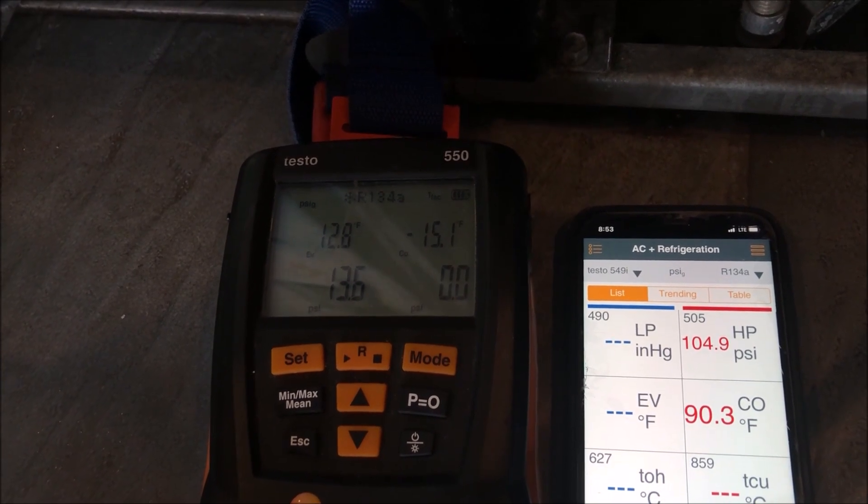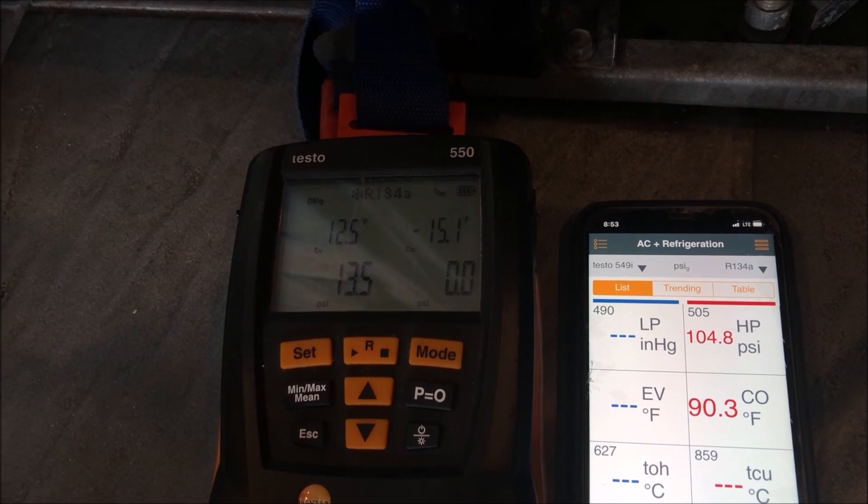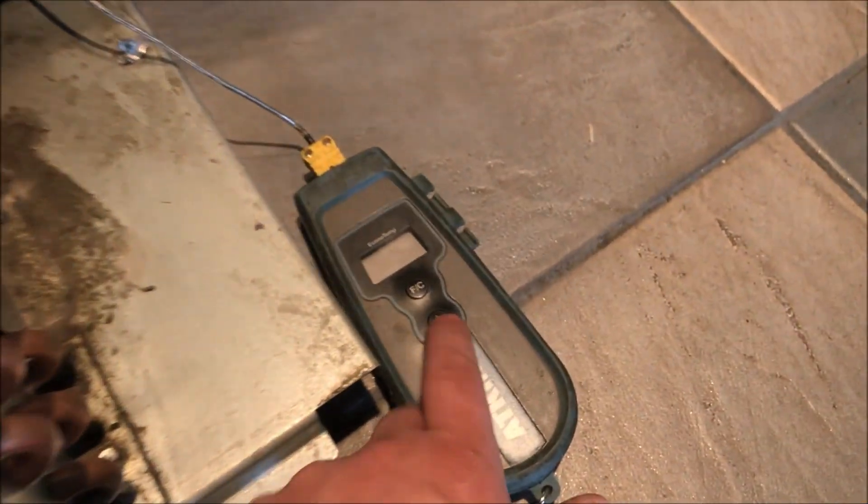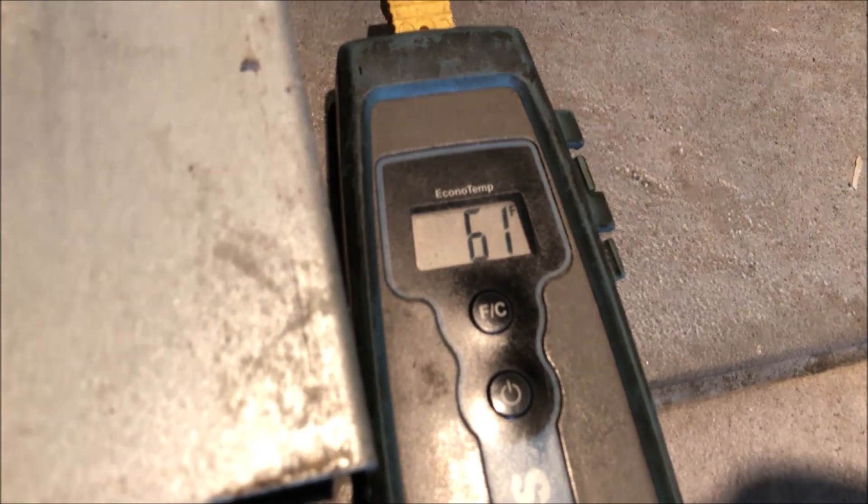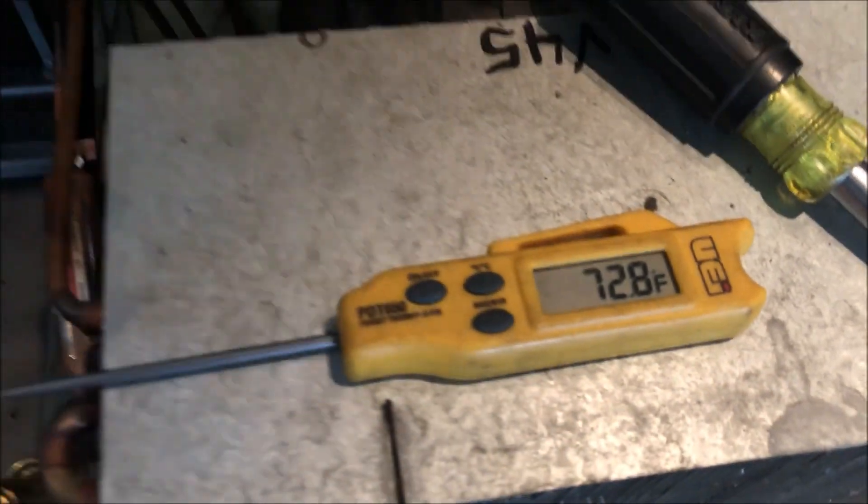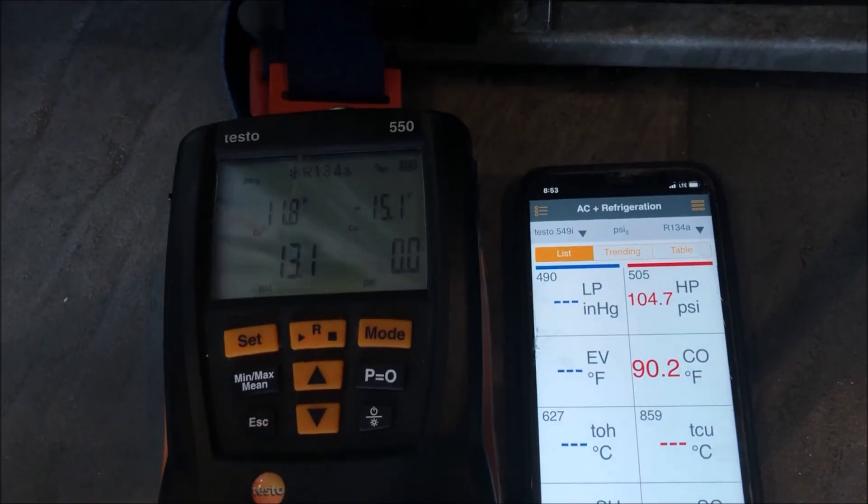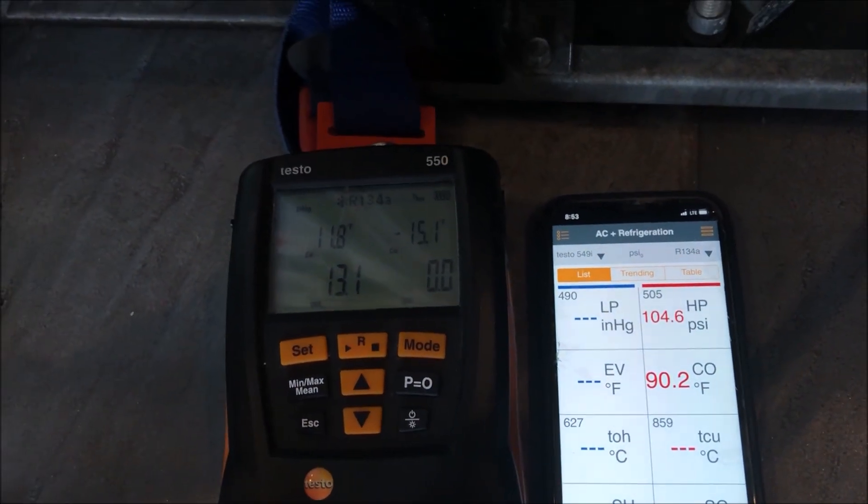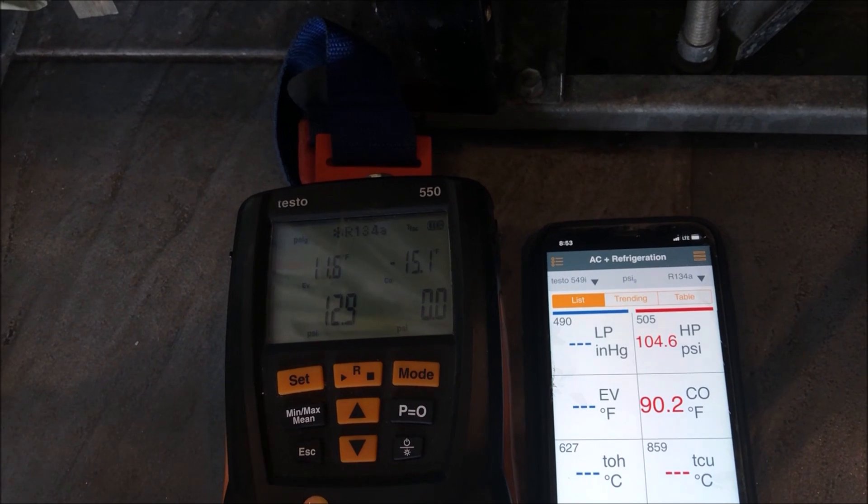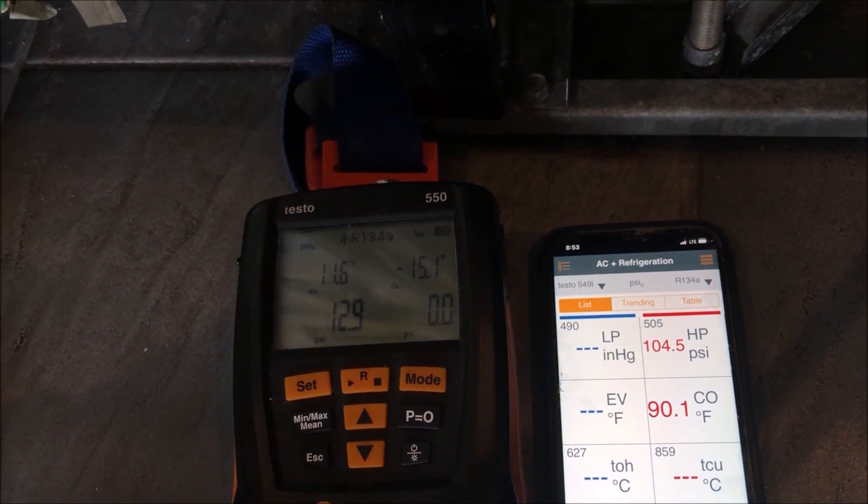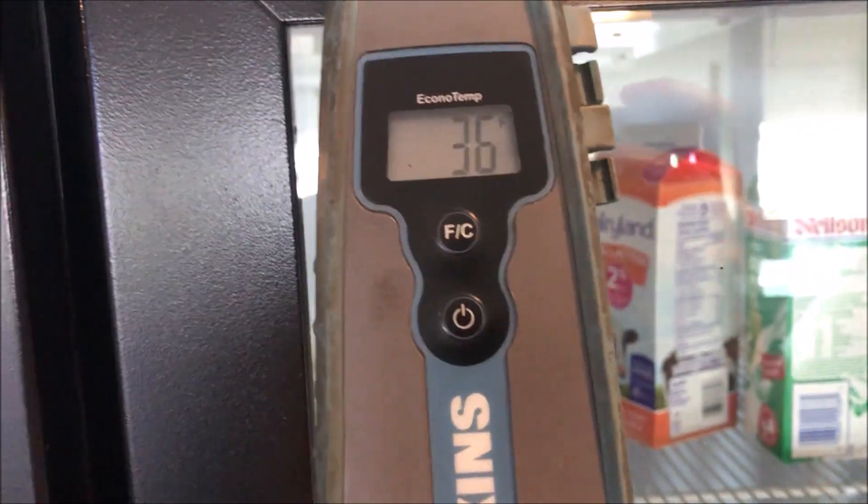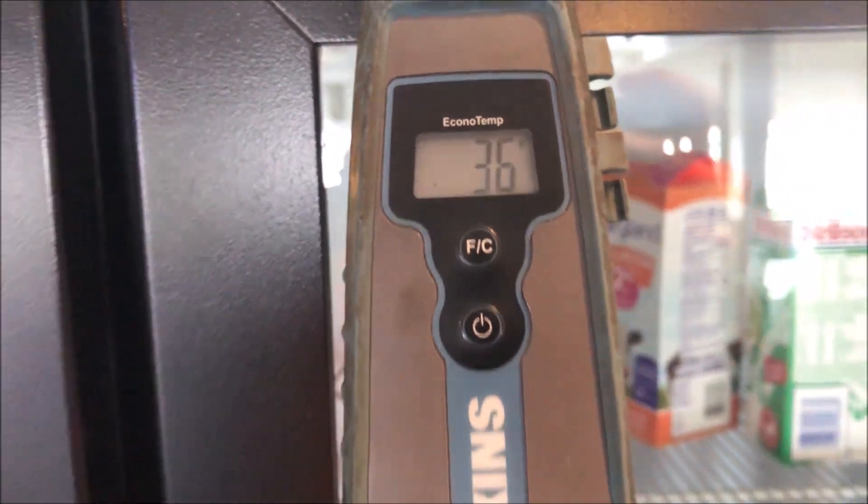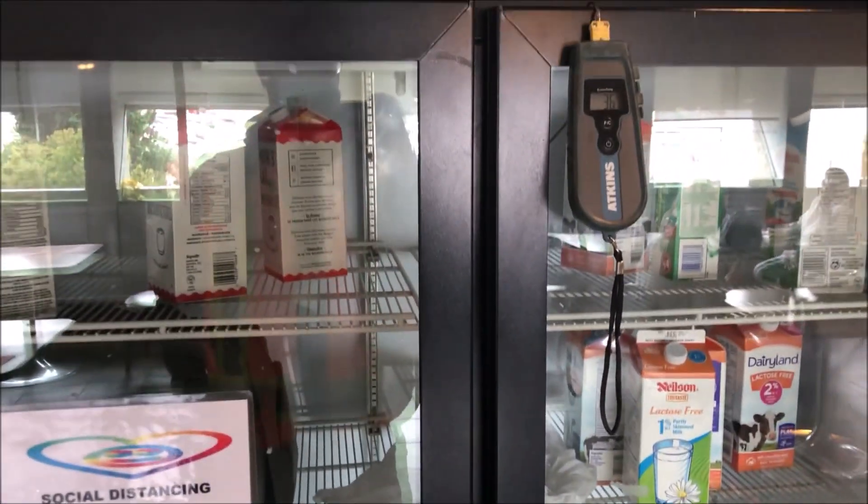We're at 61 box, so let's wait patiently. Let's see if this thing's gonna drop. Actually we're up to 73 ambient temperature, so that would give us an 88 condenser saturation. We're two degrees off there, that's fine. And we are at temperature, 36, 36 Fahrenheit. We are all good.